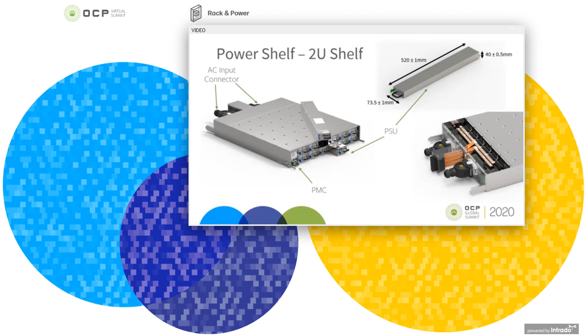This is the Universal Power Shelf Input Connector, which we showed in the previous slide with the 1U shelf. It is a 7-pin connector which is configurable as star, delta, or single phase. Each can accommodate up to 32 amps. The latching mechanism on the input cable is also toolless, and the connectors are keyed to prevent inappropriate assembly or any other issues.